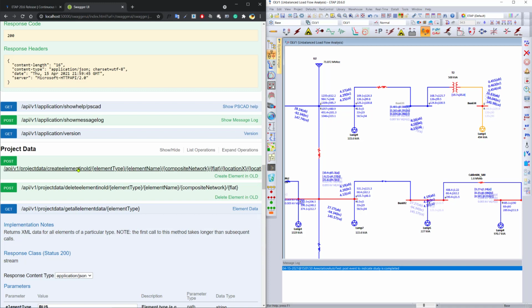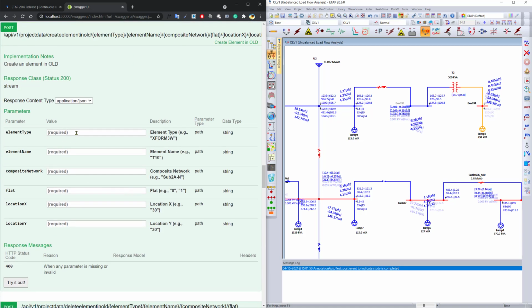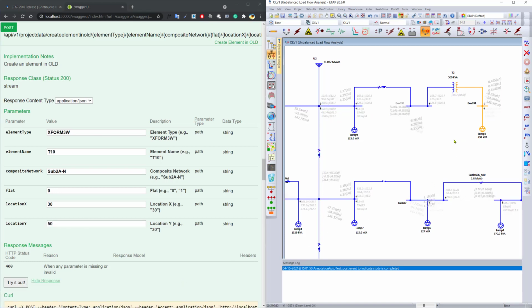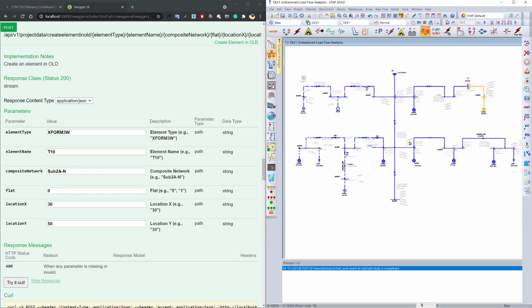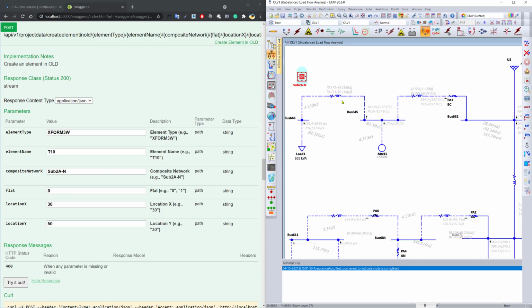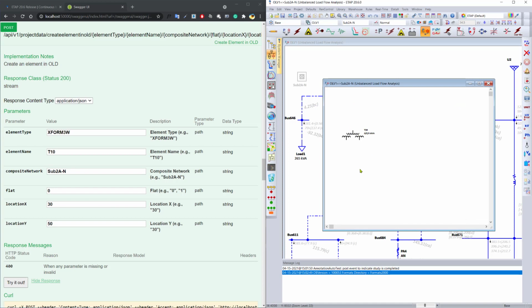calculations. The other power of the program is its ability to also now create elements based on your command. You can use the create element method to create the element of your choice. I would like to go ahead and create a three-winding transformer called T10 inside a composite network sub 2AN. It will be flat, which means it will be available on the main diagram, and it will be created on location 30 by 50. And we can go ahead and apply it and zoom out to see our new transformer inside sub 2AN that has been created for us with the ID T10.